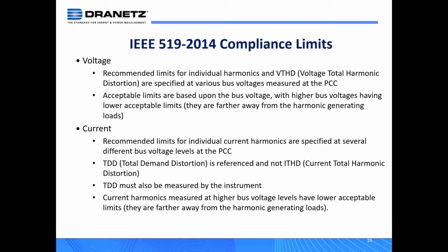So the generators, whether that be a DER or solar or a gas-fired generator, produce very pure sine waves. So it's the loads that we plug into the electrical system that produce the harmonics. As we get closer to those loads, as the voltage goes down, as we're closer to the consumer of power, the acceptable limits have to go up a little bit because that's where these harmonics are originating from. But conversely, when you go up through our distribution systems and transmission systems, that's not where these harmonics are originating. So the higher voltages mean you're farther up the system, closer to the generation, and the lower the acceptable limits are, because if you get harmonics, they reflect up to that point, and it's more of a major problem because everyone has to deal with them in the system. So hopefully that was clear.